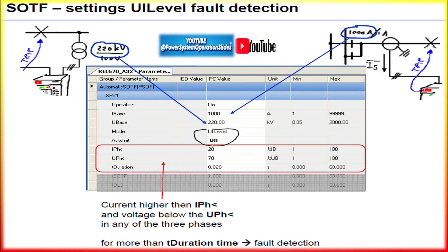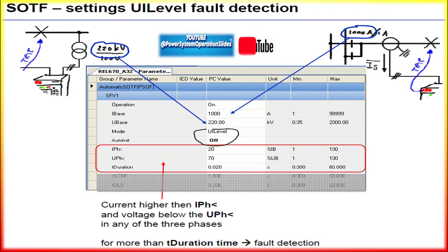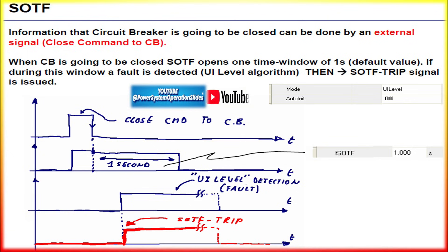SOTF differs from regular fault detection in that regular distance protection relies on zone-based measurement, where the relay measures the impedance of the line, and uses time delays to ensure selective tripping of the proper circuit breakers. SOTF bypasses zone-based protection — normal distance relay zones 1 and 2 may not have time to operate during an SOTF event because the fault must be cleared very quickly. SOTF operates on different logic: it uses a combination of breaker status, low voltage pre-closing, and high current post-closing to detect a fault, rather than relying on impedance measurement.